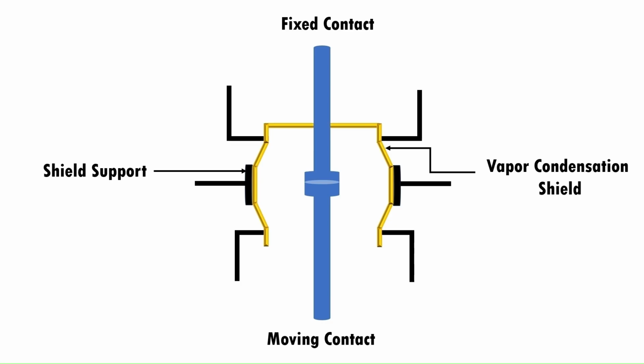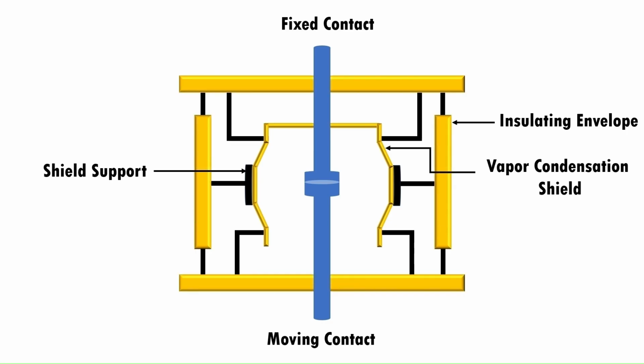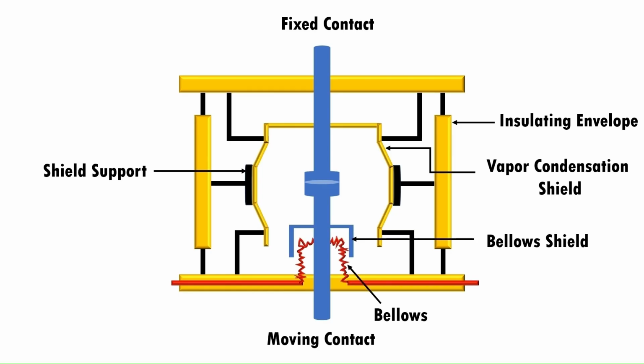The outer insulating envelope of vacuum circuit breaker is made of glass because the glass envelope helps in the examination of the breaker from outside after the operation. If the glass becomes milky from its original finish, then it indicates that the breaker is losing the vacuum. The metallic bellows made of stainless steel is used to move the moving contacts. The design of the metallic bellows is very important because the life of the vacuum circuit breaker depends on the ability of the component to perform repeated operations satisfactorily.